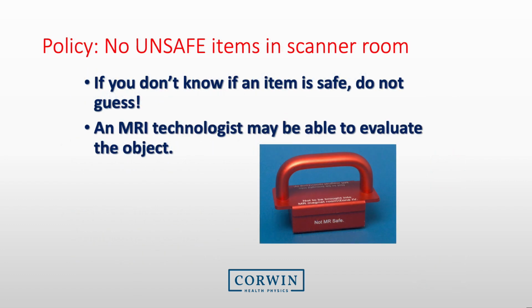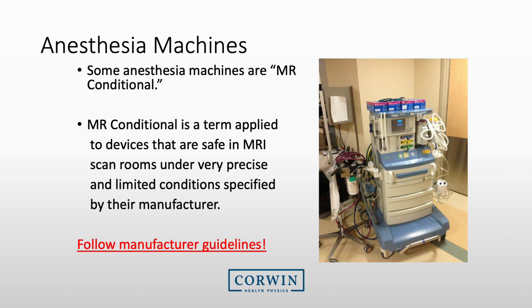So every facility has a policy that no unsafe items are taken into the scanner room. If you don't know if an item is safe, do not guess. Make sure someone evaluates the item. Here's an example of an item that is conditional. This anesthesia machine may enter the MRI suite, but only under certain conditions. You will need to review the documentation associated with any equipment to ensure you meet those conditions before you let them into the MRI room.